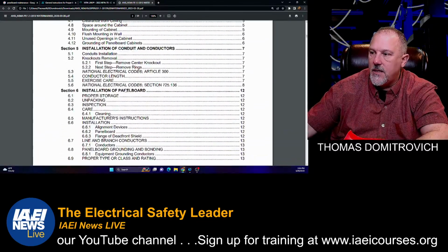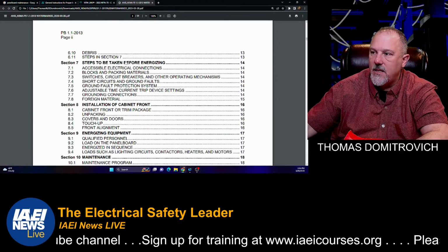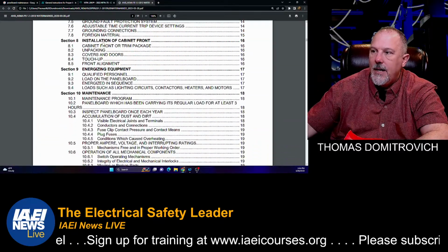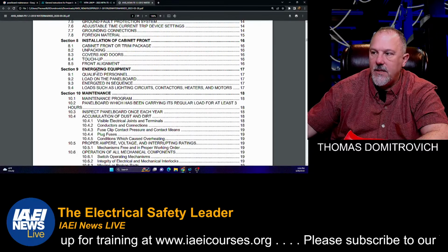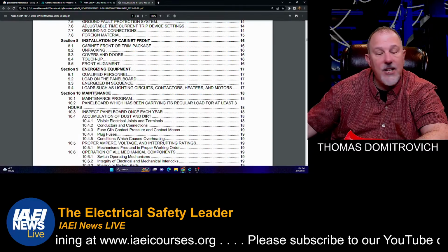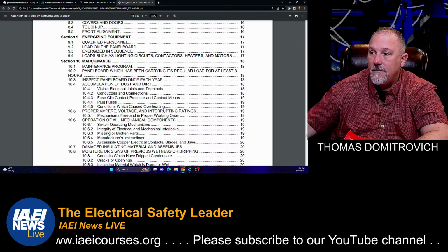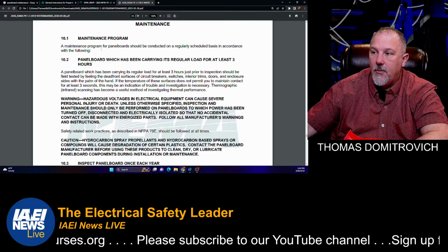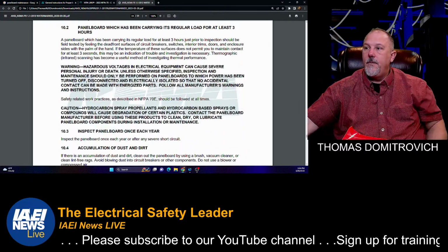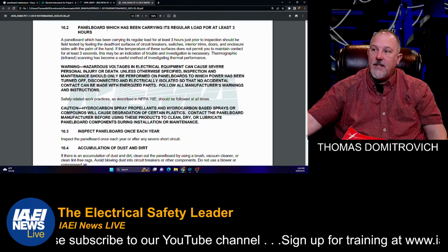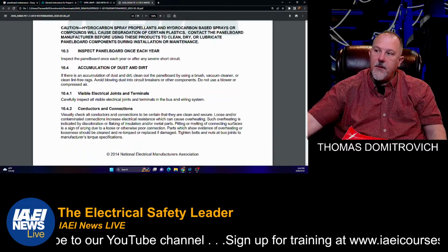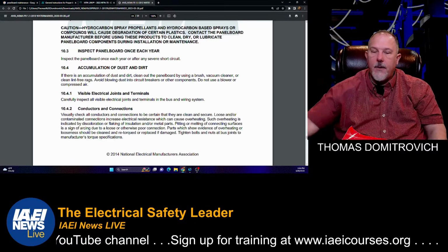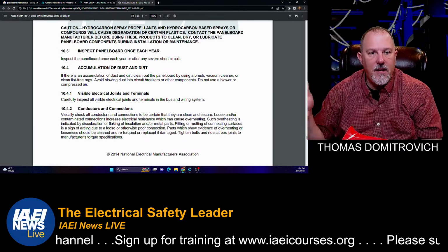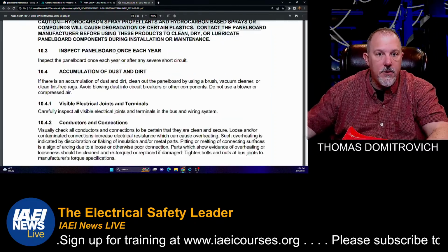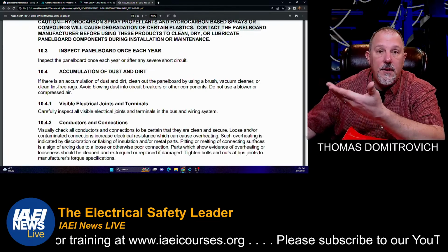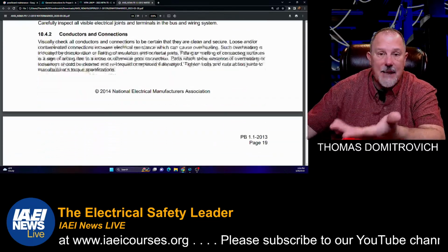Chapter 6 is installation of panel boards. Chapter 7 is steps to be taken before energizing. Chapter 8 is installation of cabinet fronts, energized equipment. And Chapter 10 is maintenance — you have the program there. So this is another great reference for you, because it was developed by all of the manufacturers of panel boards, and they all agreed on these steps to take for maintenance.